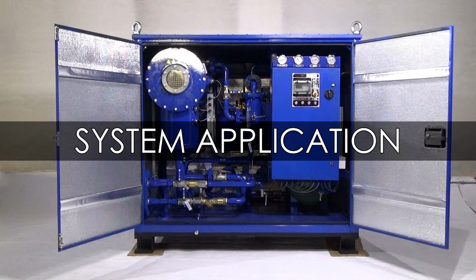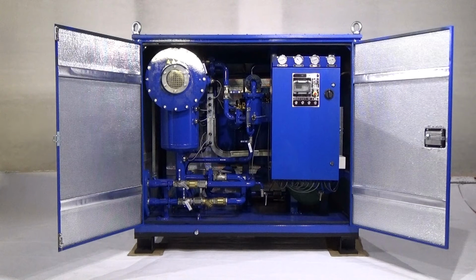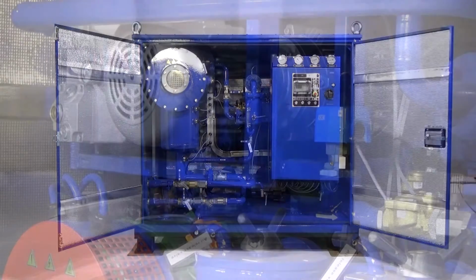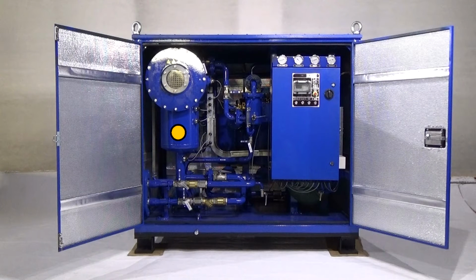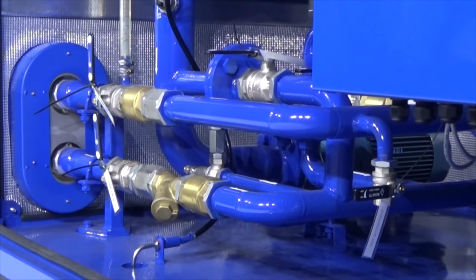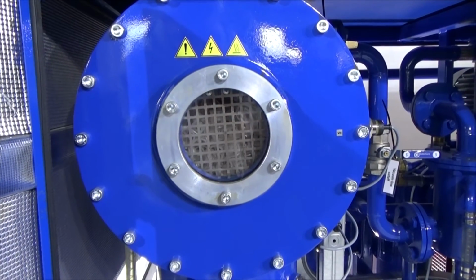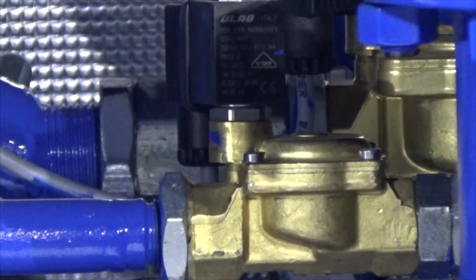System application. The mobile oil unit is designed for comprehensive purification of turbine oils, removing water and particulate matter. Principle of operation. The vacuum pump creates vacuum in the vacuum chamber. Vacuum draws the oil into the chamber. The oil passes from the inlet line through the mesh filter, the heater, electromagnetic valves, and into the vacuum chamber.